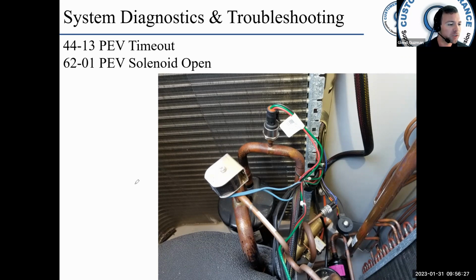So let's see, PEV opens for 2.5 minutes, or it opens 2.5 minutes after the compressor shutdown if the pressure differential is between 200 and 300 psi, or if the pressure differential is greater than 50 and a demand is present. In both cases, the PEV will open until the differential is less than 40. You get 4413 when the PEV is open for 10 minutes and it does not reduce the pressure differential below 40. According to the manual, if this occurs, it's likely that the valve or the coil has failed. Replace the coil and harness first. If the fault persists, replace the PEV valve itself.